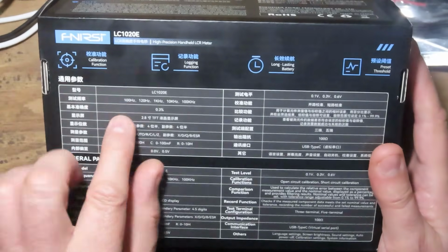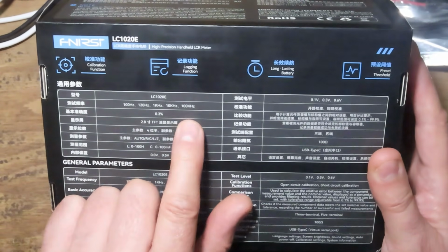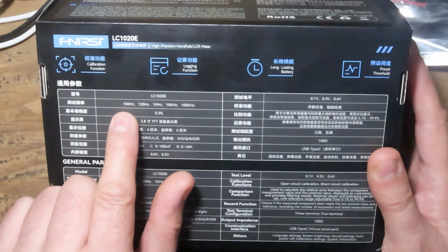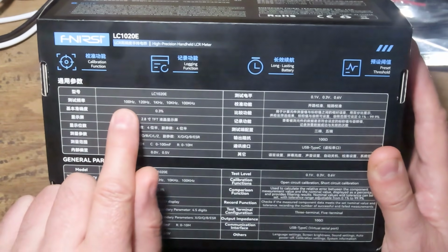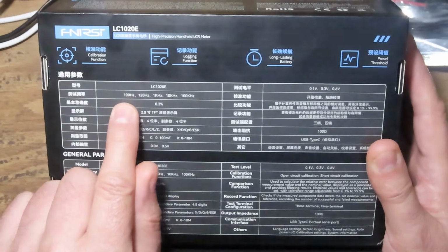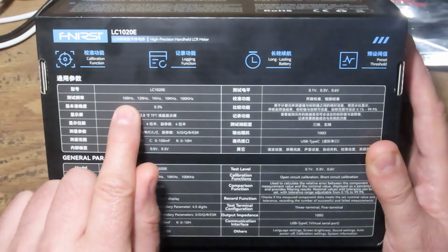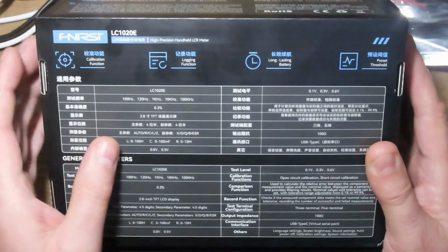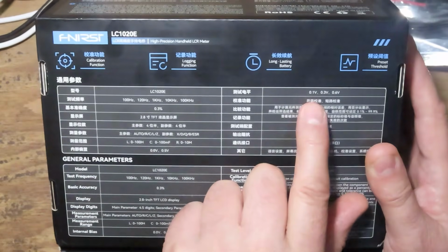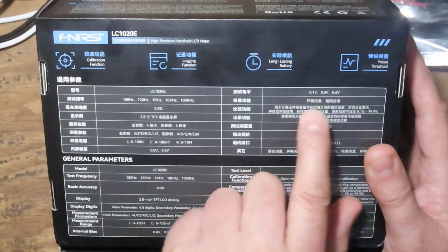We do have several frequencies from 100 Hertz up to 100 kilohertz. And it's good that it goes down to 100 Hertz. You want a very low frequency if you're testing capacitance, especially if you're going to try to test the quality of a capacitor in circuit, which is possible to do because this will also operate at a very low voltage, from 0.1 to 0.6 volts.